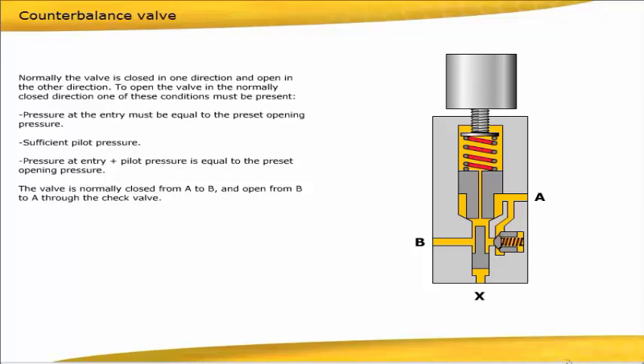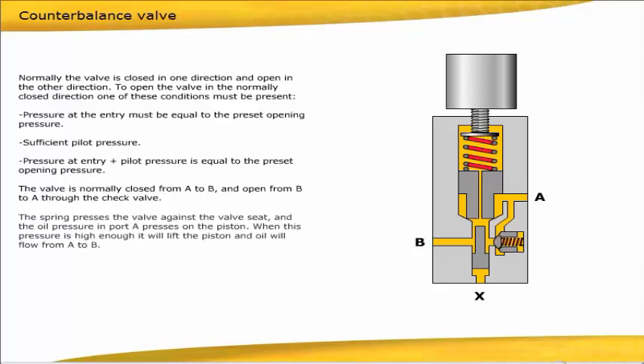The valve is normally closed from A to B, and open from B to A through the check valve. The spring presses the valve against the valve seat, and the oil pressure in port A presses on the piston. When this pressure is high enough, it will lift the piston, and oil will flow from A to B.